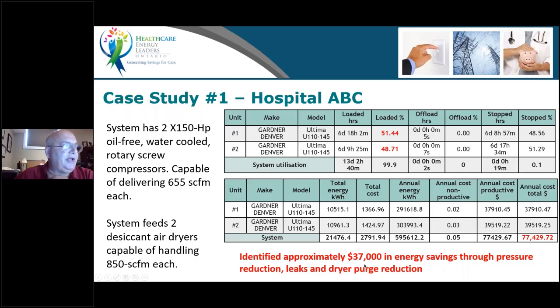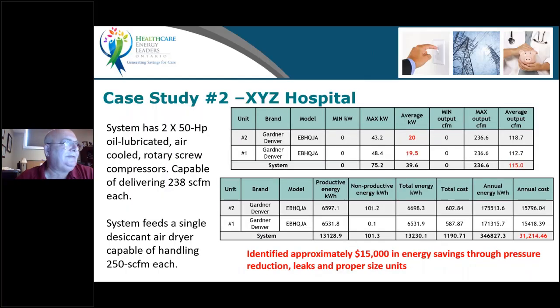The dryers are desiccant type on 655 SCFM, so every time they purged and regenerated, it was almost 15% of that, about 100 SCFM they were using just on the purge on desiccant dryers, which they didn't need. That type of drying system, refrigerated, would have done. But there was an opportunity there to reduce that purge and cut energy costs.